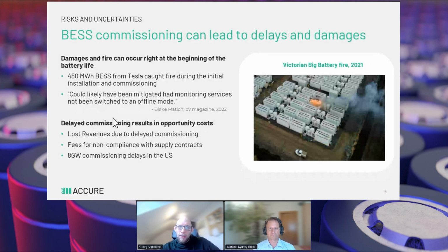Here on the right-hand side, you see an example of the Victoria Big Battery fire in 2021. This was a 450 megawatt hour battery energy storage system from Tesla, which caught fire during the initial installation phase. As PV Magazine pointed out, this likely could have been mitigated had the monitoring services not been switched off.